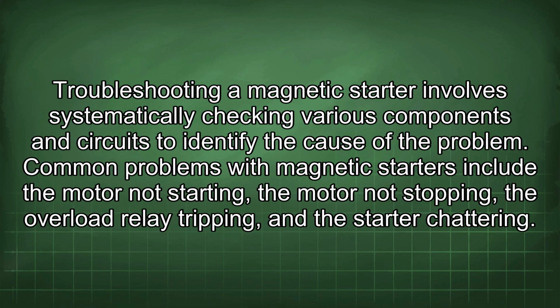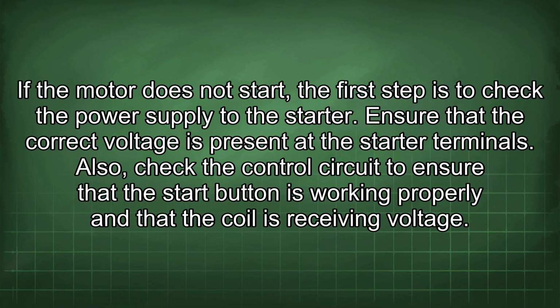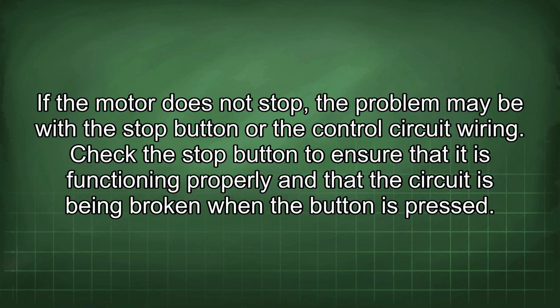Troubleshooting a magnetic starter involves systematically checking various components and circuits to identify the cause of the problem. Common problems with magnetic starters include the motor not starting, the motor not stopping, the overload relay tripping, and the starter chattering. If the motor does not start, the first step is to check the power supplied to the starter. Ensure that the correct voltage is present at the starter terminals. Also, check the control circuit to ensure that the start button is working properly and that the coil is receiving voltage.